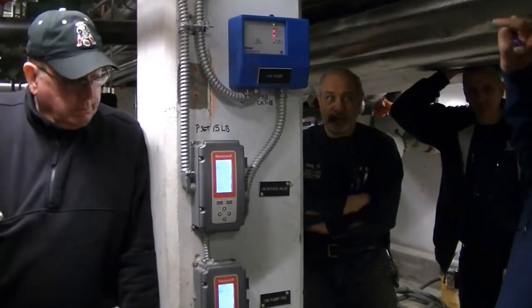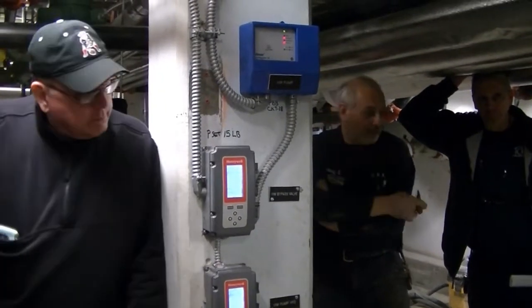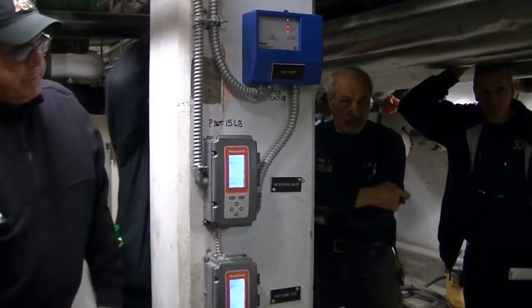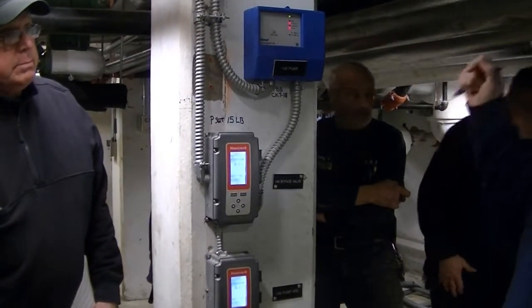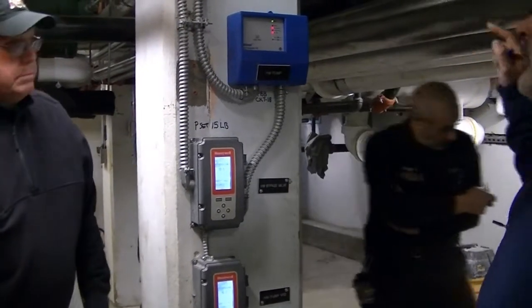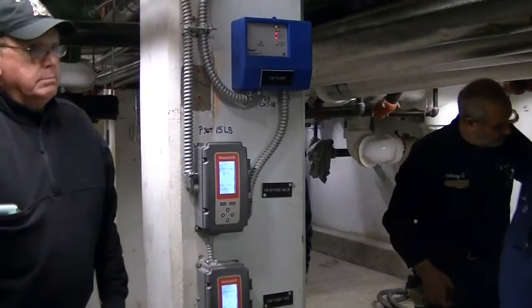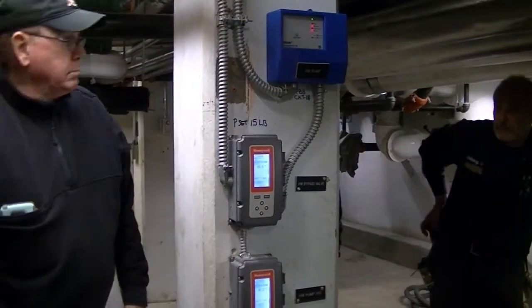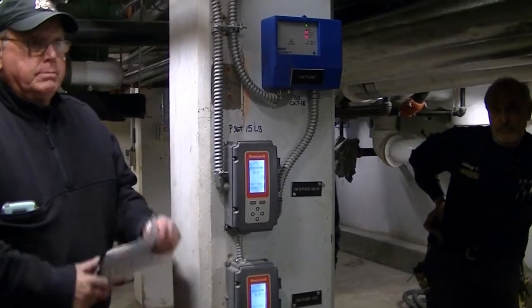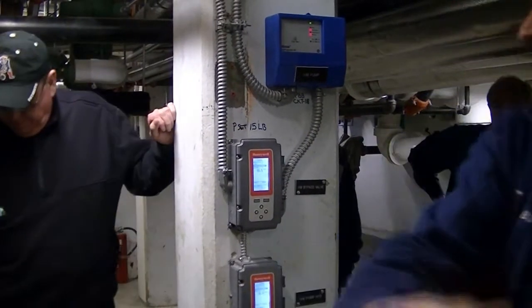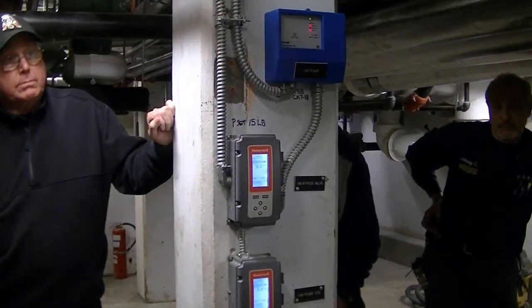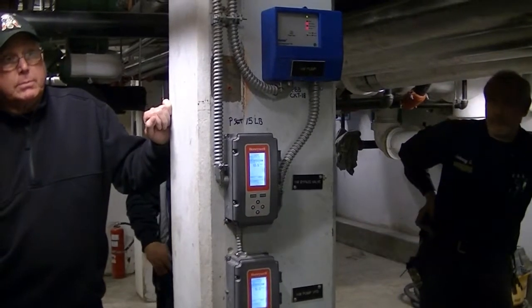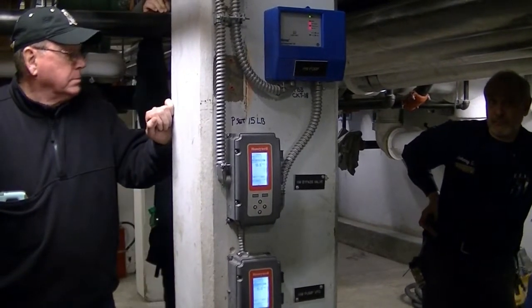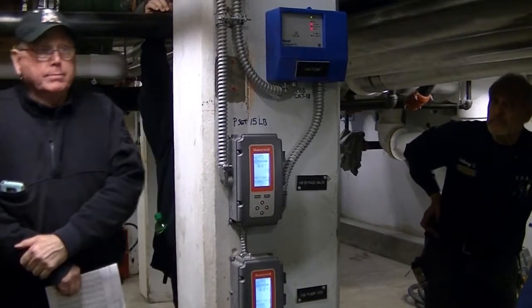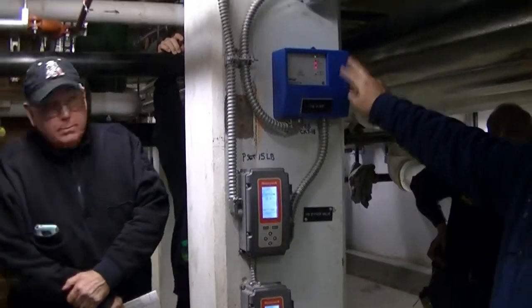What these standalone controllers do is operate the heat and hot water pumps. We've got two pumps, P1, P2 I think they're called, or P3, 4, I don't know. We've got two domestic pumps for domestic hot water. We also control the start-stop of those. And we modulate a valve, and we modulate the speed of the VFD pumps, the heat and hot water VFD, to maintain the differential pressure. So there's basically 4 controls. 3 of them are right here. One you'll see down for the domestic pumps. There are 2 pumps there. There's another one of these pump sequencers down around the corner, right behind on the wall over there.